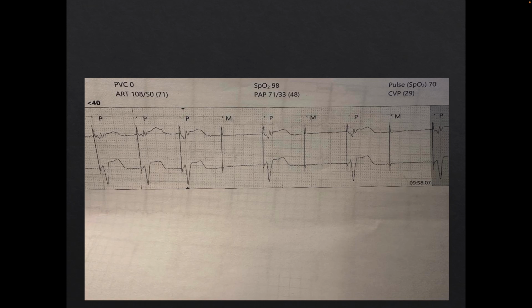So permanent devices can also sometimes have loss of capture for some of the reasons I mentioned earlier. Maybe the patient had an MI, maybe a lead moved, maybe there's a fracture issue, there's something else going on, that's why they're not capturing. So those are all things that you want to monitor. But typically for all of you, this is going to be your TVP or your epicardial wire patient. If they don't have output, you want to increase your mA.